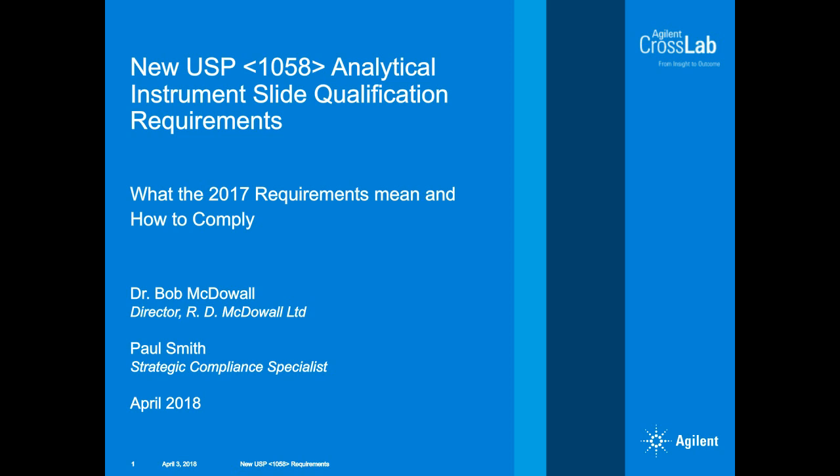Paul, I don't know if you want to add. Yeah, I think same as Bob really. By consistently applying a process-based approach that includes risk assessment and includes all of the elements, you then consistently follow the process, but where it's a category or group A, for example, where you verify the operation by observation, it's important that observation occurs at the point you're using the system rather than independent from it. So, for example, you will always examine glassware for chips and marks, etc., before an analyst uses it.